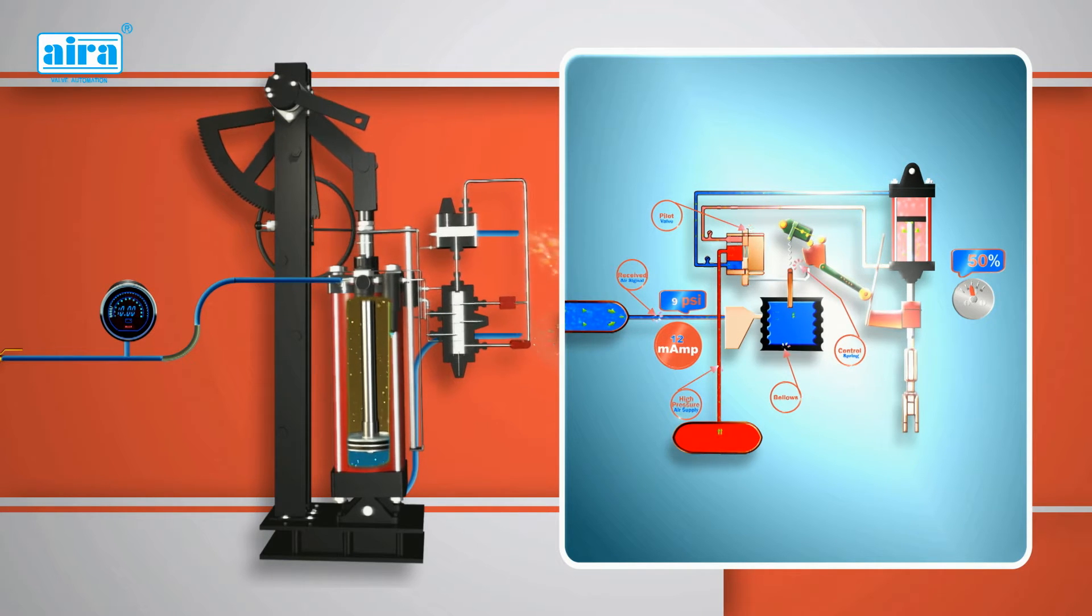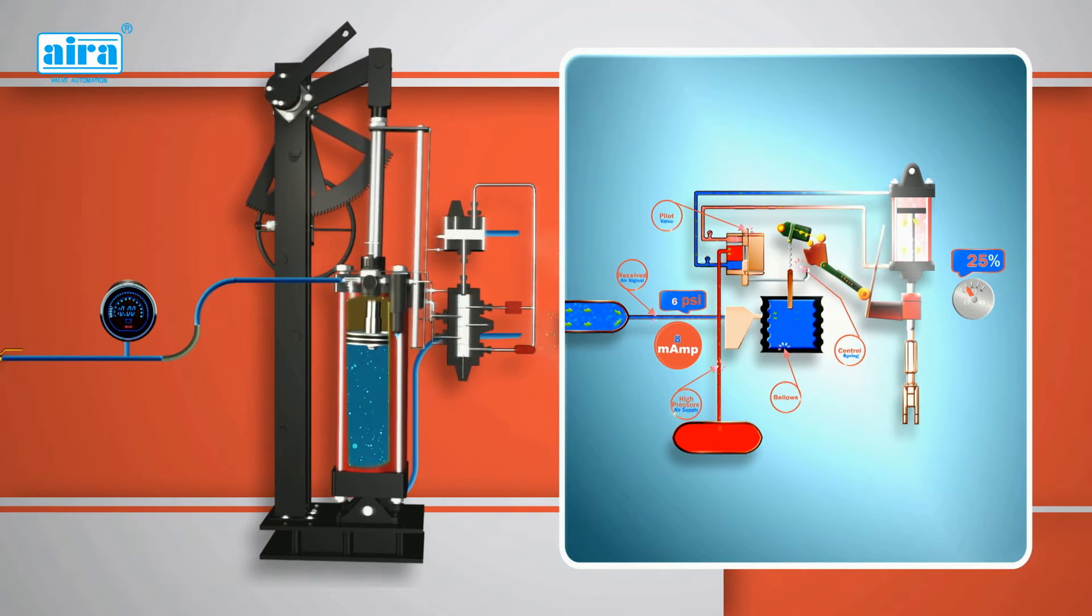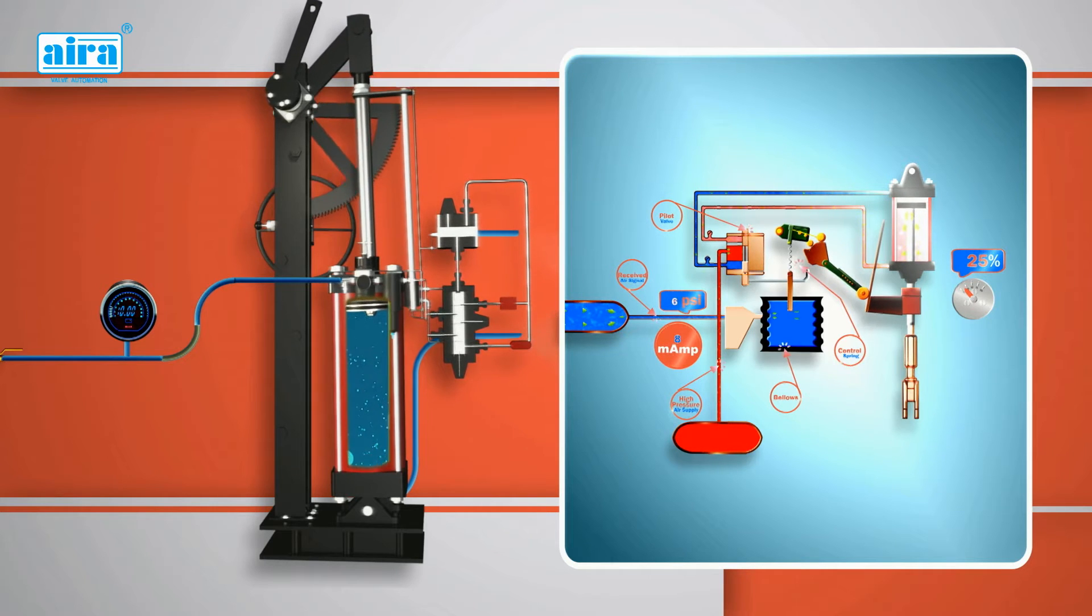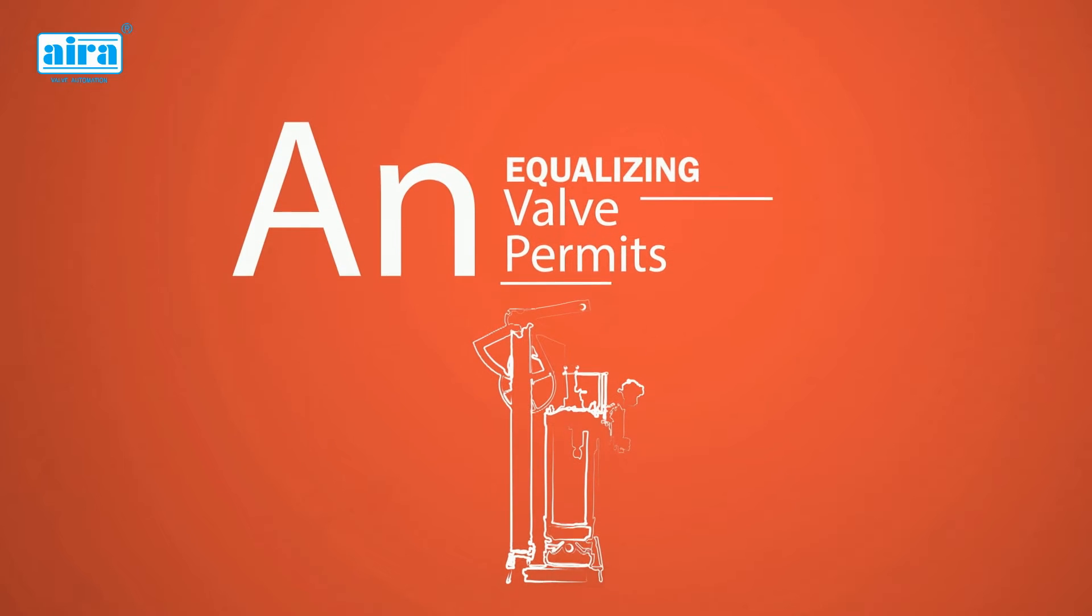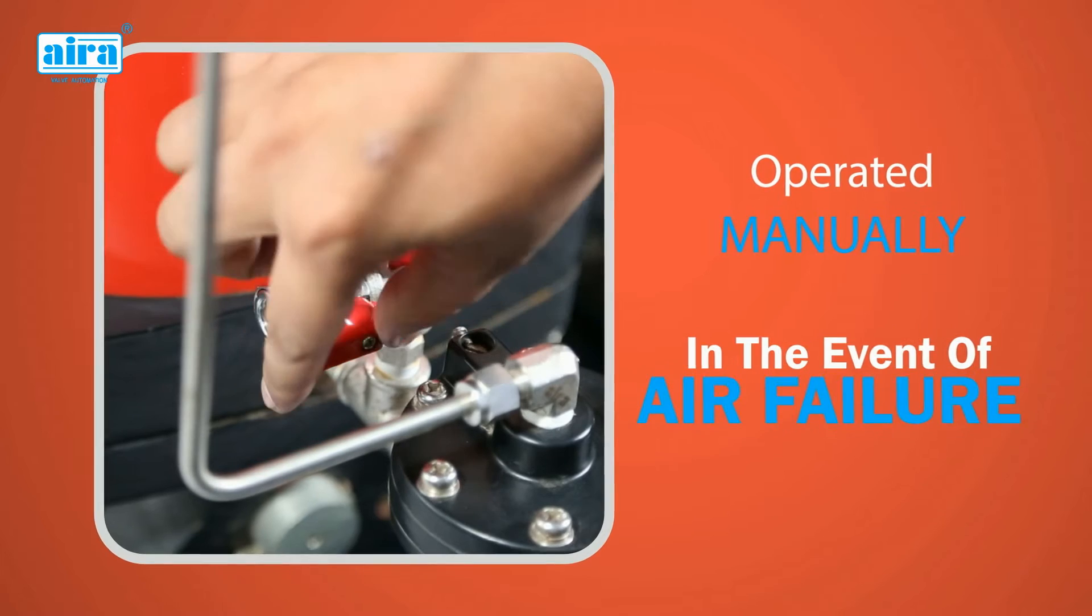The pilot valve is then closed and the piston comes to rest in its new position. Cams can be supplied to give either a linear or logarithmic relationship between the control signal and piston position. An equalizing valve permits the power cylinder to be operated manually in the event of air failure.